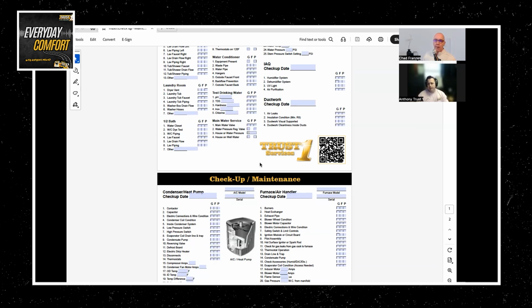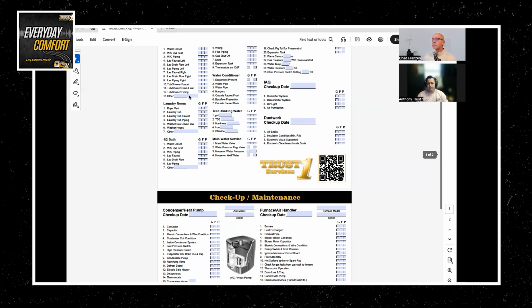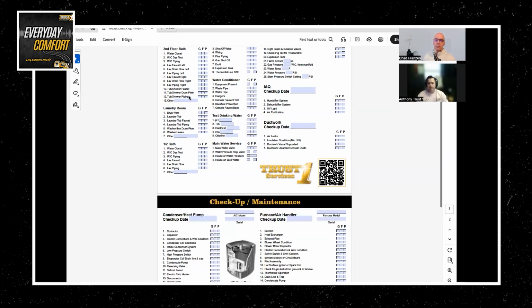Or if you have a gas furnace, you might not feel the difference. Has there ever been a case where fixing an air duct maybe made a bigger difference than replacing equipment? Yeah, honestly, it's a huge component of the system. In some cases, if they have high utility bills and the system's in decent shape, it might be better to do the ductwork before you replace the system, because you're literally taking a system out and putting a brand new system into an entire system that is not properly done. So you're literally shortchanging the life of the unit by not addressing the real problem.